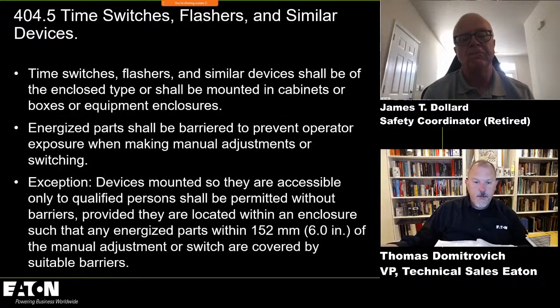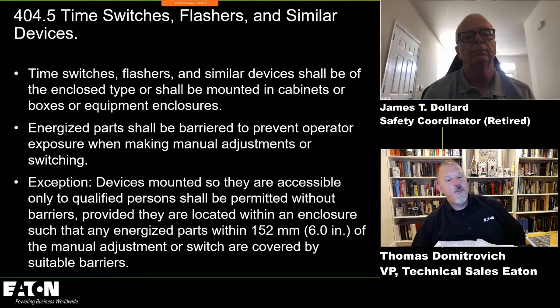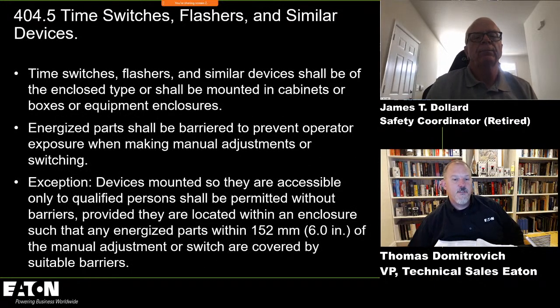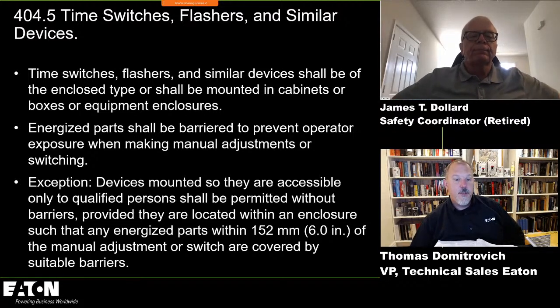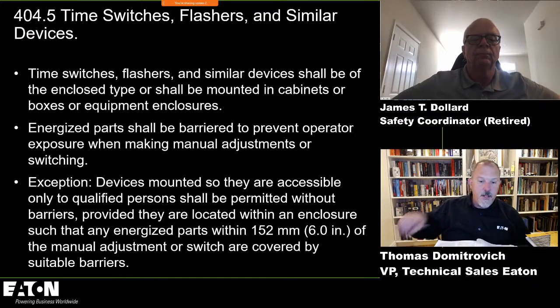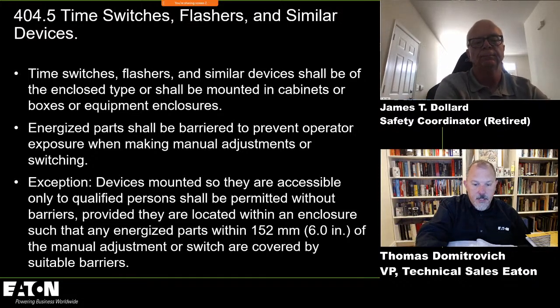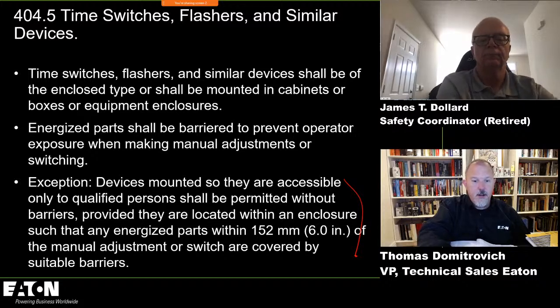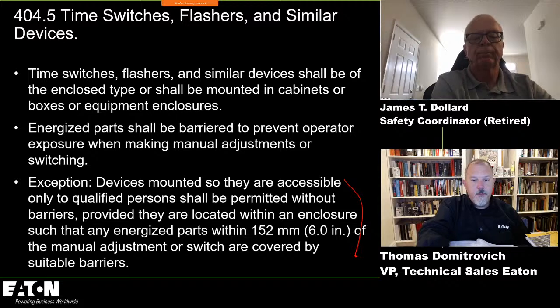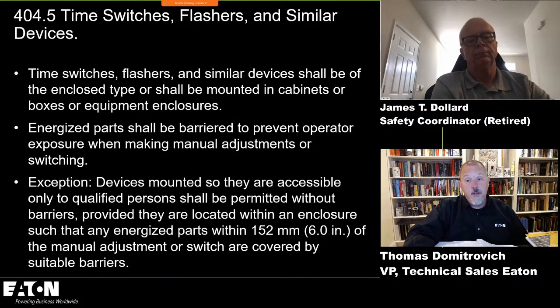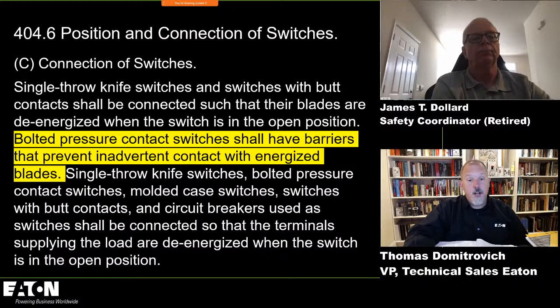All right. So that was good. And then I went back up to 404.5, timing switches and flashers. There's dialogue in there about requiring barriers. I believe down here on the bottom, if I'm not mistaken, permitted without barriers provided they are. Yeah. So this is just providing some more barriers to prevent operator exposure. So it's all about ensuring nobody comes in contact and reducing the likelihood of shock.